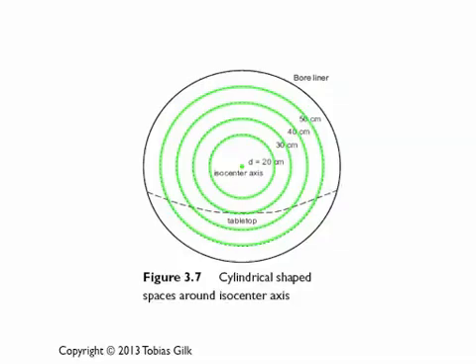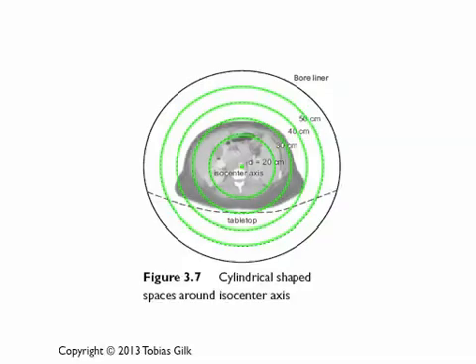We don't really care what the patient is exposed to biologically — the patient has been prescribed an MRI. What we're concerned about is the magnetic field acting on MR conditional implants and devices. The first thing we need to do is figure out where the implant or device is within the patient, and then determine where that anatomy falls within these concentric bullseye rings — within the 20, 30, or 40-centimeter ring.